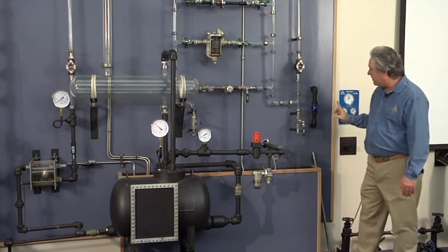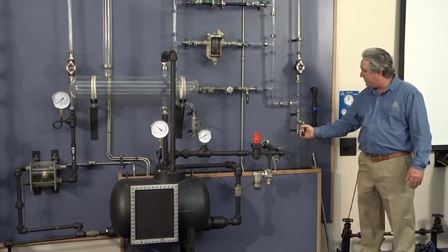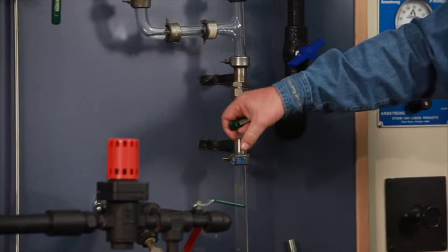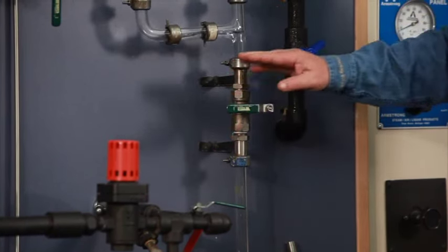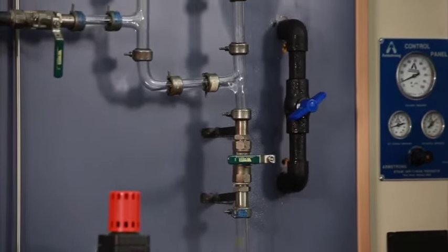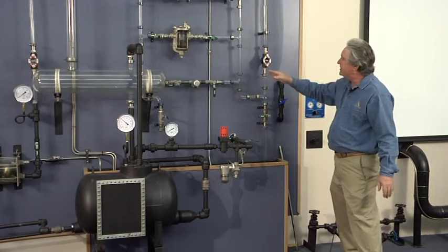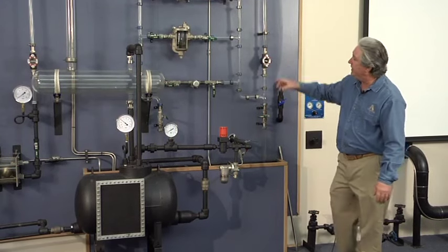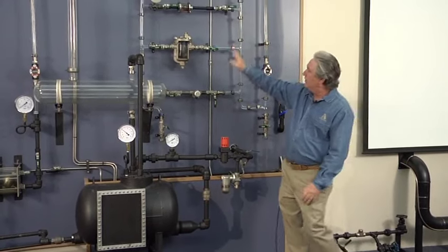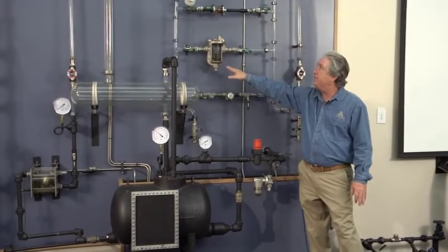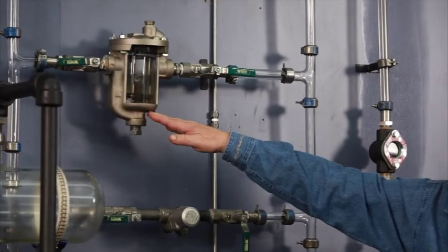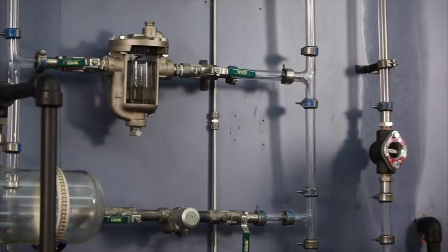What we're going to do now is I'm going to slowly valve out this atmospheric valve. And we're going to slowly, as you can see, start to build up level in the condensate return piping. As you see the condensate being drained through the trap, the differential initially on this trap was 5 pounds. We had 5 pounds on the outlet of the heater coming to the trap. We had 0 psig at the drain.